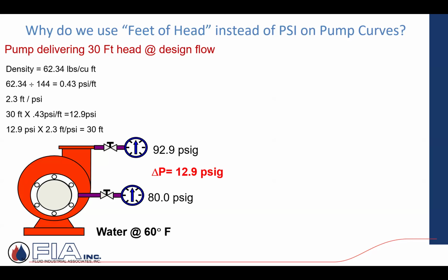Let's finish with this last example. It's answering the question: when I look at these pump curves, why am I using feet of head instead of PSI? Everything's listed in GPM on the bottom and feet of head on the vertical left. So the pump is delivering 30 feet of head. I'm dealing with 60-degree water, and I'm developing a differential of 12.9 PSI. With 62.34 pounds, as we talked about for 60-degree water, 30 feet times 0.43 PSI is 12.9 PSI. So if I look at the suction gauge and it had 80, and when the pump turned on it developed 12.9 PSI, I know that 12.9 PSI with 60-degree water is 30 feet of head.